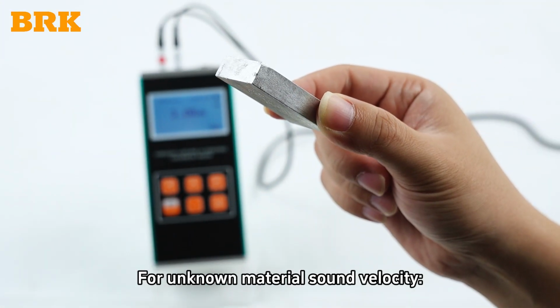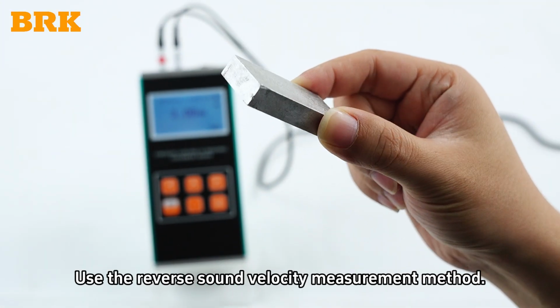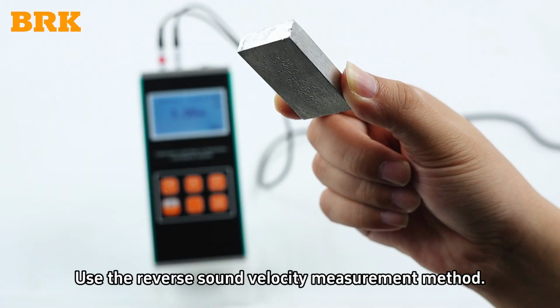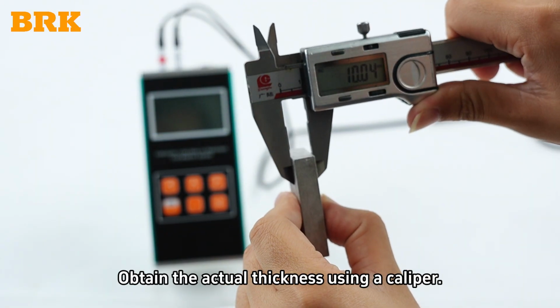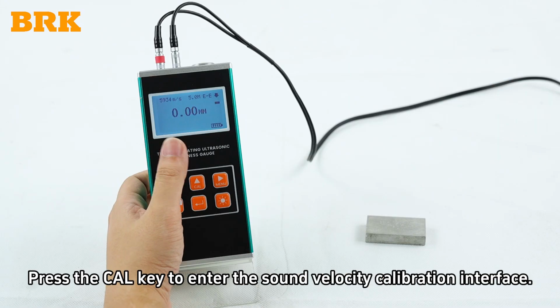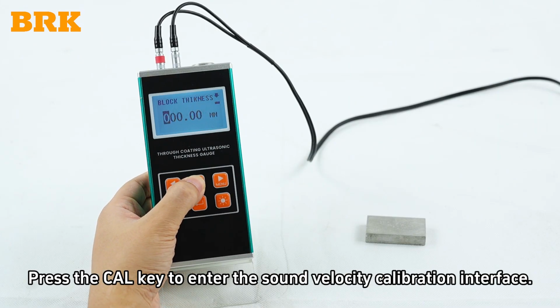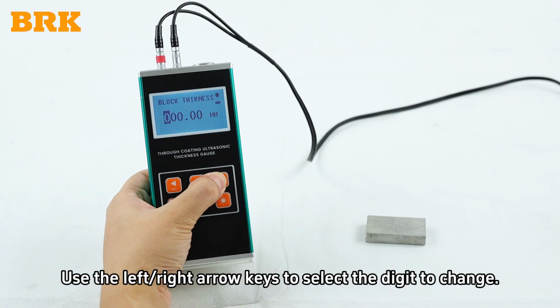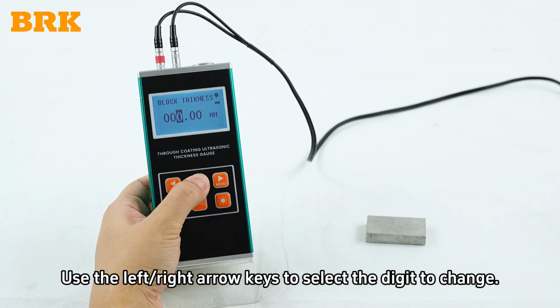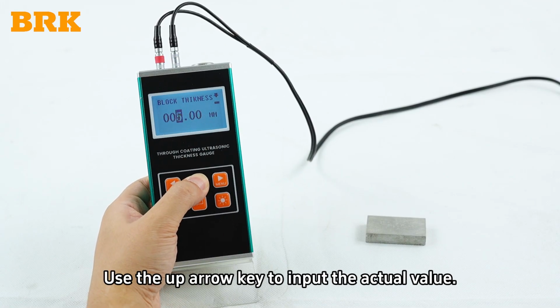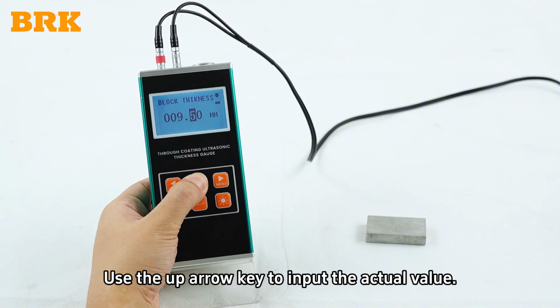For unknown material sound velocity, use the reverse sound velocity measurement method. Obtain the actual thickness using a caliper. Press the Cal key to enter the sound velocity calibration interface. Use the left or right arrow keys to select the digit to change. Use the up arrow key to input the actual value.